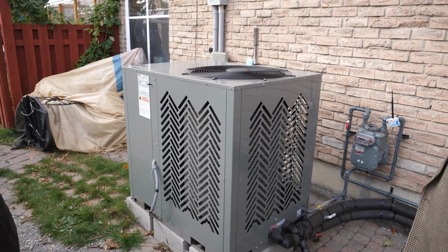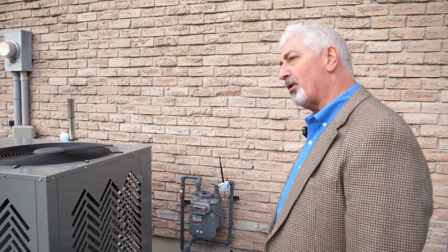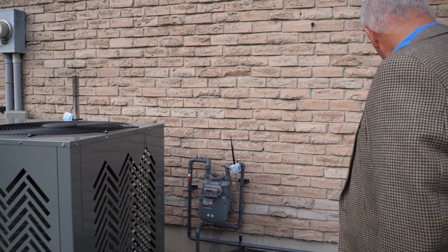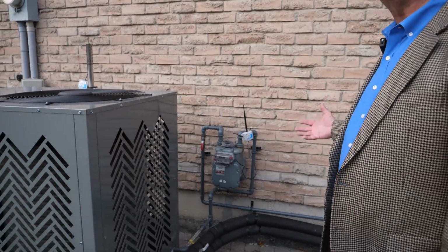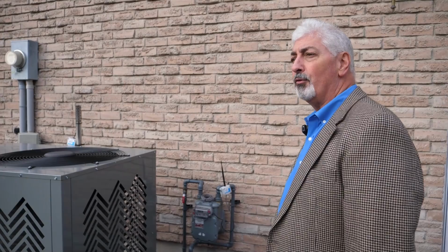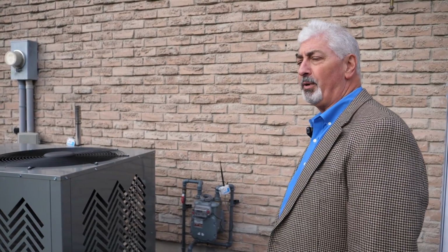It's a great protection, and in our installation training, we offer contractors two options. They can either run the lines in a secure fashion above ground. Obviously, they want to insulate them. You're going to penetrate the house in some reasonable manner. Airex happens to be one of the devices that we use, but it can also be buried as well. So you can go through the penetration into the house below grade, as long as you've got it well secured, watertight, and well insulated.